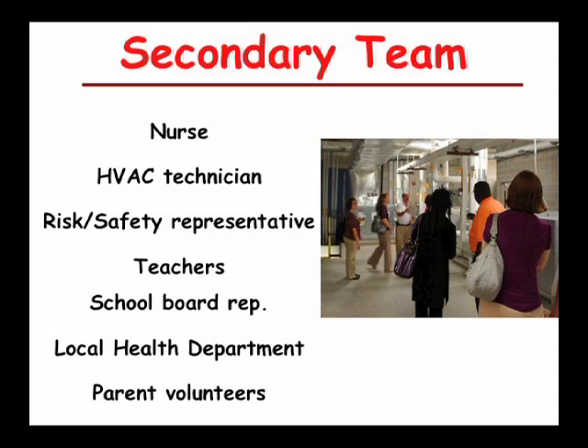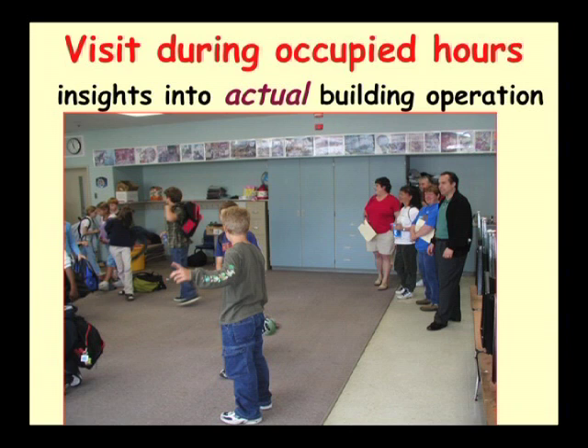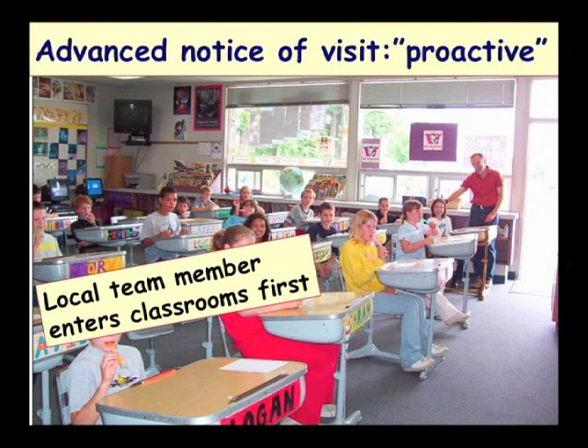If the team gets a little unwieldy in size, remember that everyone doesn't have to enter each classroom to minimize disruption during the five or ten minutes inside. Before starting for the day, have a brief sit-down with the team to make sure everyone is on the same page. Agree that any sampling results or values would be posted right away in the staff room with business cards of people who can answer questions, that the walkthrough is the first step toward a more formal IAQ program, and that whatever is observed, corrective action will be prioritized with appropriate timelines. We want to see schools during normal occupied hours at full capacity, engaged in customary activities — we need the occupants' breath to do our carbon dioxide diagnostics of fresh air ventilation. Staff should be warned well in advance that we're coming and that our walkthrough is routine, not in response to a crisis.